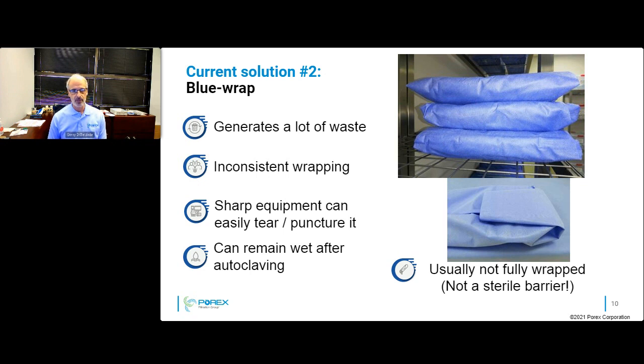A scalpel or any kind of pick can easily go through it, and then any kind of sterile barrier you had is gone. Another problem is these things can have moisture go through them, especially if they're not sealed well. And then when you open up your package, it can remain wet inside. So it's definitely not a sterile barrier, even though the blue wrap companies will tell you that it has a BFE rating, bacterial filtration efficiency rating, of 70, 80, 90, 95%. That assumes that the product is completely sealed off. Any kind of openings or crevices within it will reduce that bacterial filtration efficiency dramatically.